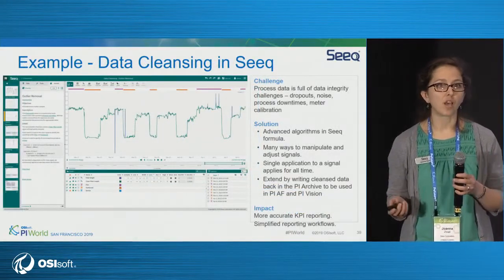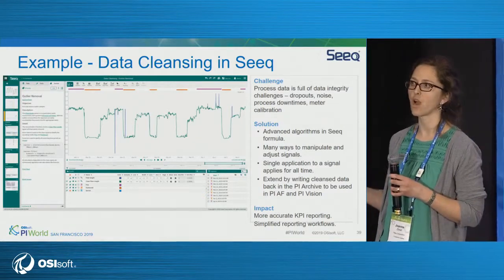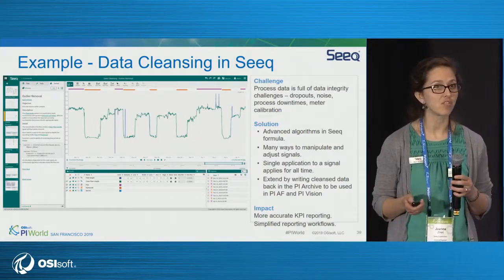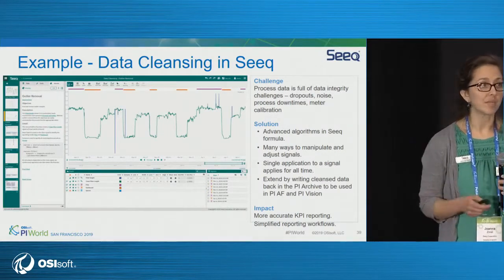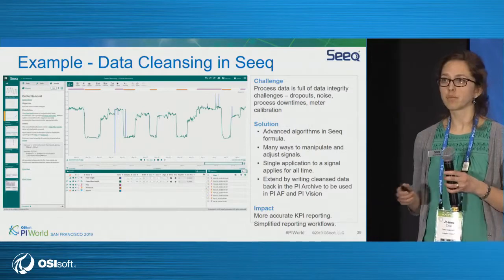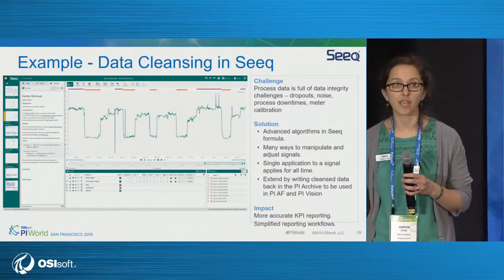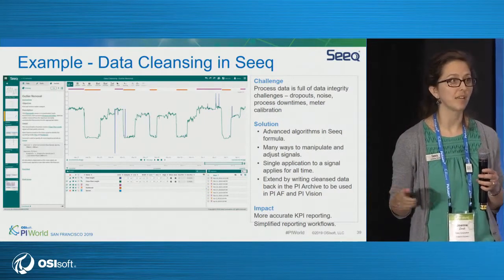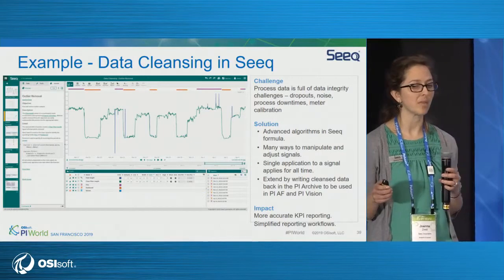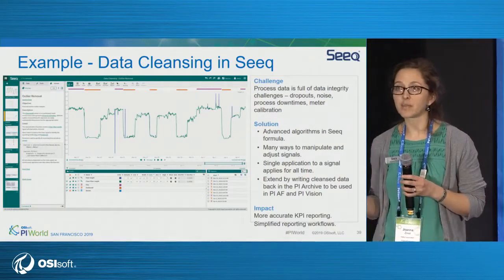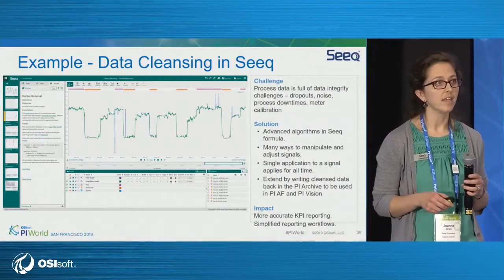One way Seeq is often used in this industry is in data cleansing. Data is wrought with difficulties. Sometimes the noise is interesting, sometimes it's not. There can be dropouts that need to be filtered out. Whenever your plant is down for any reason — planned maintenance — the flow meters do some wonky things. If you take an annual average, that's not really representative. You want to filter that kind of data out when you're summarizing your KPIs, and maybe there's instrument calibration you want to account for.